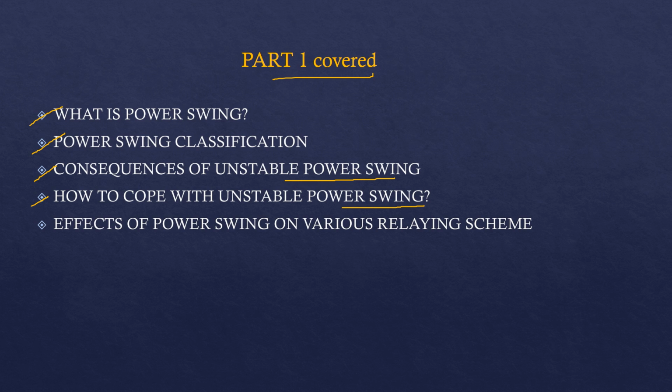Then we have discussed the effect of power swing on various relaying schemes, and by this we concluded that the differential protection technique doesn't respond to the power swing and therefore is not influenced by it, but relaying schemes like distance relay, overcurrent relay and directional relays are influenced as a result of power swing.